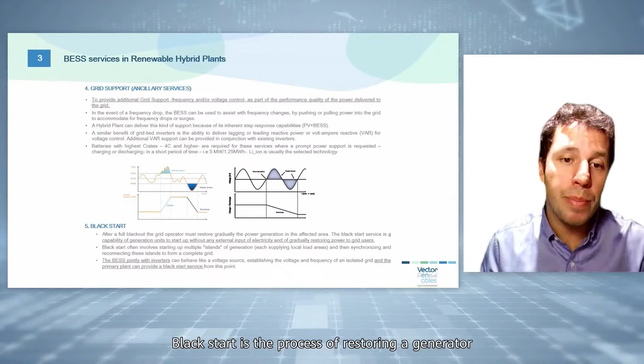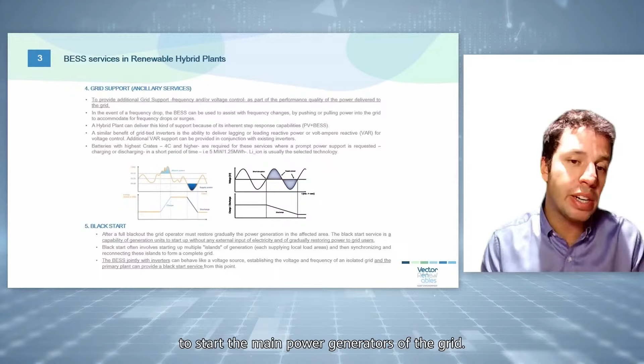You can see how this would play out on the 2 sample graphs presented on the slide. How the BESS allows for the system to have much smoother outputs. The idea is to keep a more stable output power and a more stable energy profile. Potential applications in PV are during the sunrise and sunset of the plant, as well as during variations due to passing clouds. And the usual C-rate of batteries to support these services is around 2 C, with a typical ramp rate control slope of 1% of power plant nominal power per minute. This application is currently required in several parts of the world, such as specific areas of Japan and Puerto Rico. Our impression is that this service is going to be widely implemented by grid operators, as it allows the control of the instabilities in the grid due to the intermittent nature of the renewable energy.